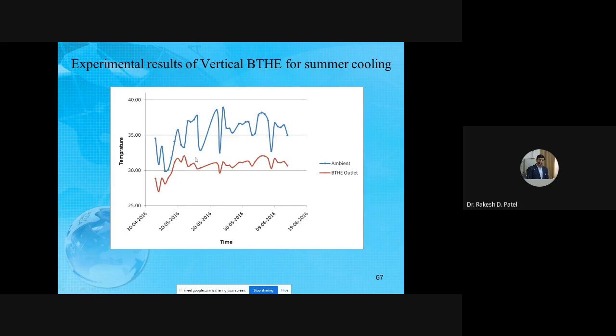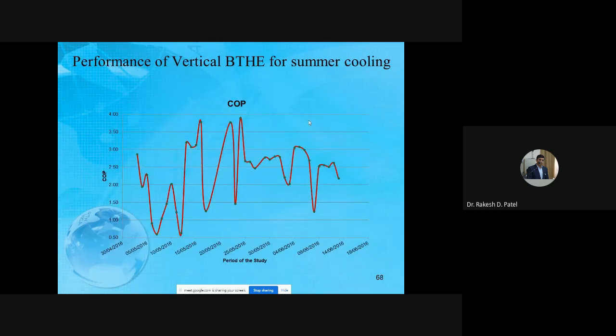So here you can see the temperature difference between ambient condition and the outlet condition of the heat exchanger. The outlet condition of the heat exchanger is approximately near 30 degrees centigrade temperature. And I think it is a very comfortable condition in case of summer as well as in the winter. Now, the COP, the performance of the vertical heat exchanger for the summer cooling, is approximately 3 COP in the specific period of study.